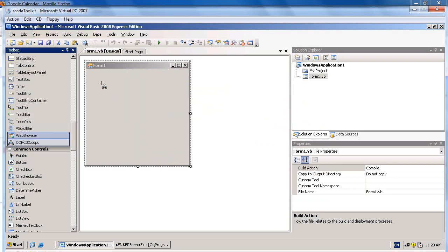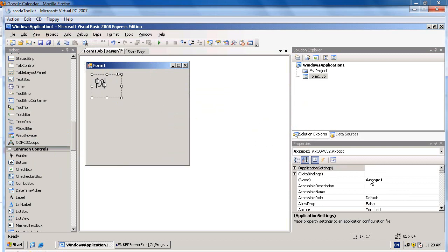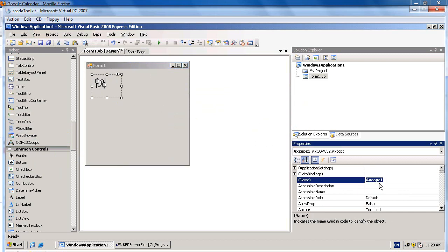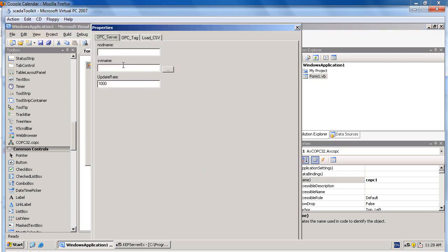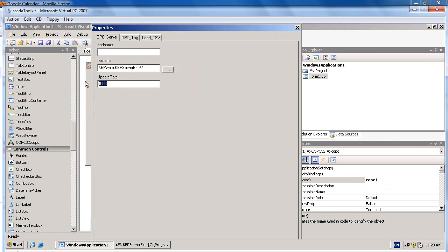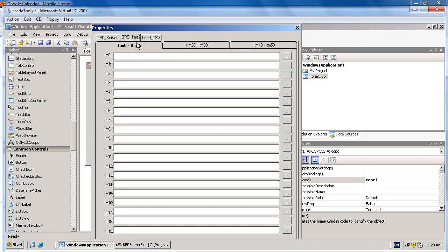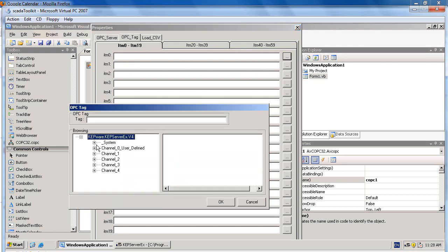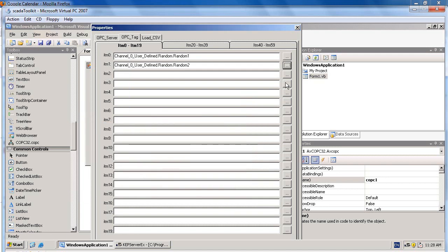Put the COPC control into the form. Please specify that its name is AXCOPC1. You can change it as well. Right-click on it and select ActiveX property to specify the OPC server and update rate. In this example, I will use 100 milliseconds. In the OPC tags tab, you need to specify the OPC tags you would like to connect.